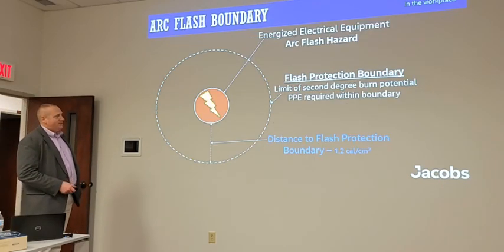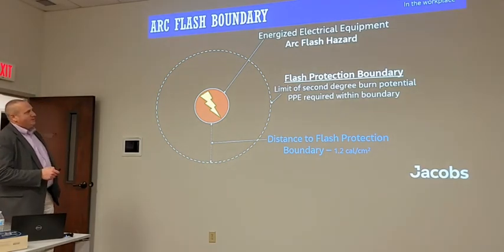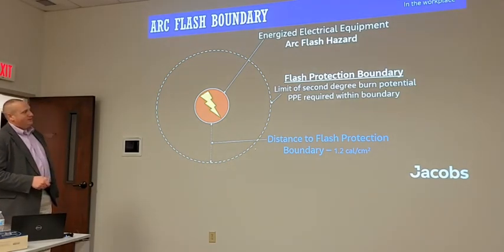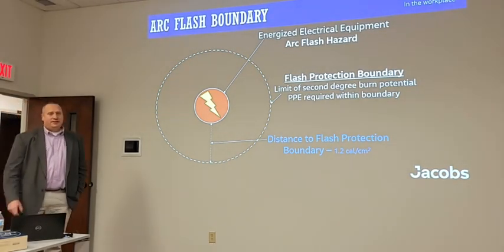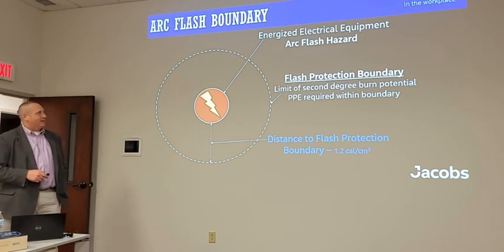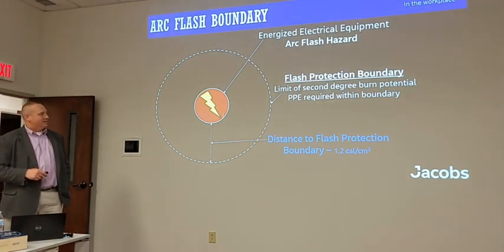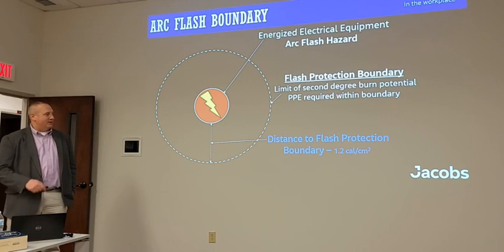So anytime you're inside the arc flash protection boundary of an arc flash hazard, you must be wearing the level of arc flash PPE that's calculated at the working area, working distance.